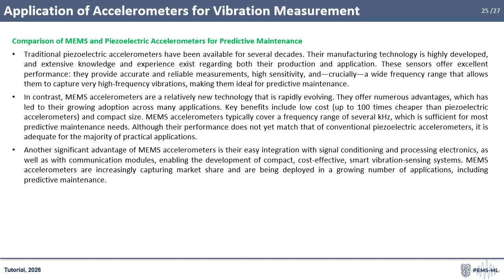Traditional piezoelectric accelerometers have been used for decades. Their technology is mature, offering accurate, reliable, and highly sensitive measurements across a wide frequency range, which makes them ideal for capturing high-frequency vibrations and predictive maintenance.